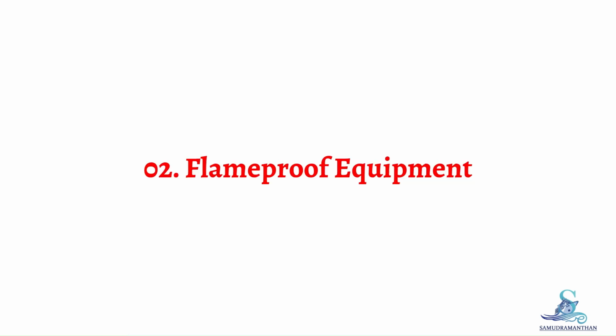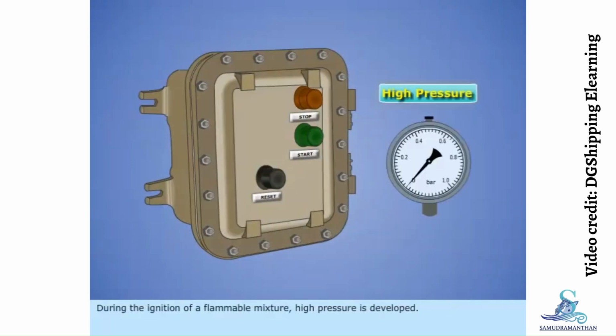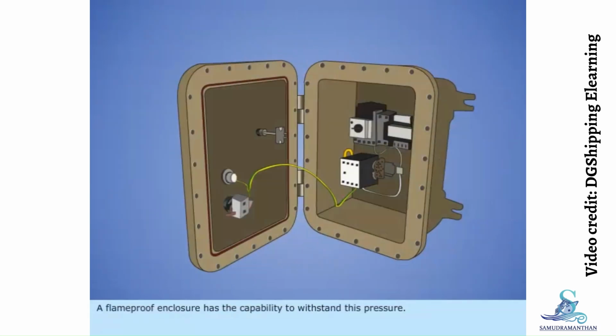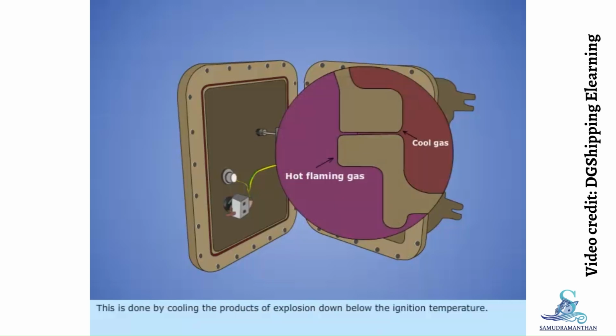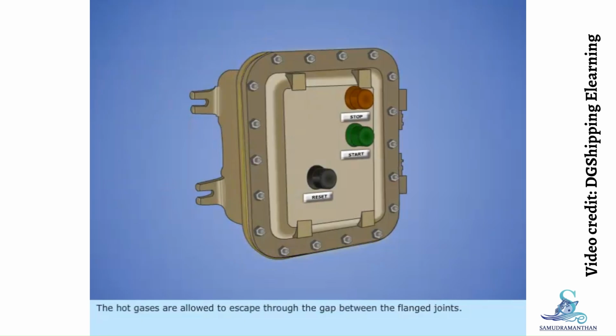Topic 2: Flameproof equipment. In this media, you will be able to learn about flameproof equipment. During the ignition of a flammable mixture, high pressure is developed. A flameproof enclosure has the capability to withstand this pressure. This is done by cooling the products of explosion down below the ignition temperature. The hot gases are allowed to escape through the gap between the flanged joints.